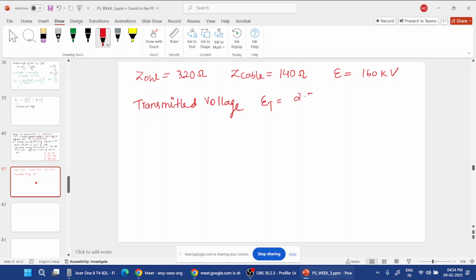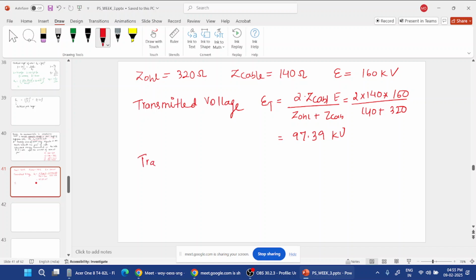Transmitted voltage ET is equal to 2 times Z cable divided by Z OHL plus Z cable. So 2 into 140 into E, also 160, divided by 140 plus 320. It will be equal to 97.39 kV.